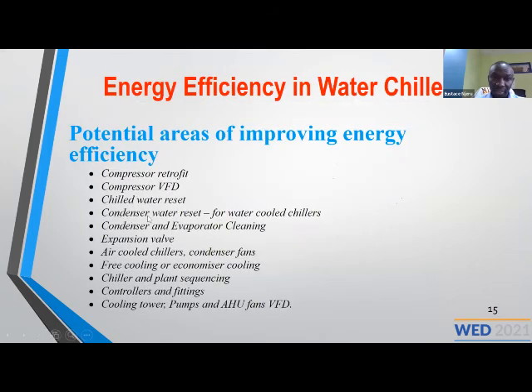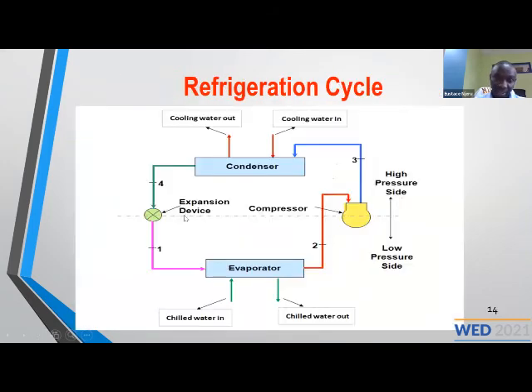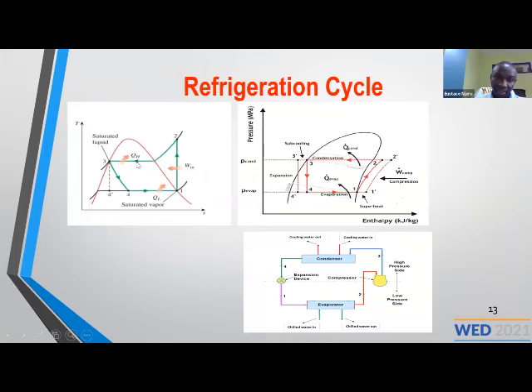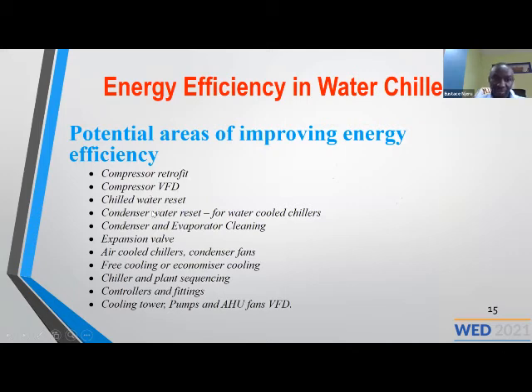The other one, you can do the condenser reset. At the same time, as we said, you need to understand this diagram. For the condenser reset, you have to check the temperature of the refrigerant and the temperature of the environment, so that you don't have to have the cooling water so cold, especially for the water cooled chillers. You don't require very low temperatures. For example, instead of releasing heat at say 23 degrees, you can design to release heat at 25 or 30 degrees, and that can save a lot of energy. And that is the scope of condenser reset.